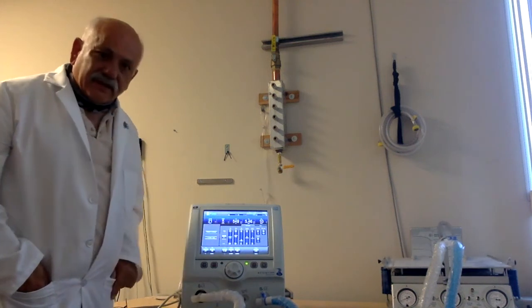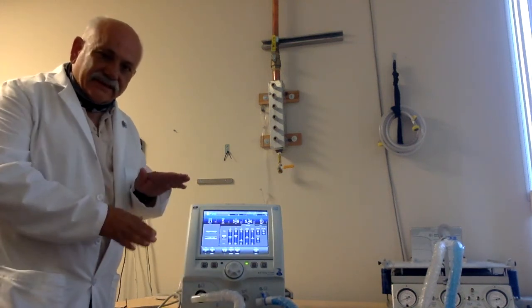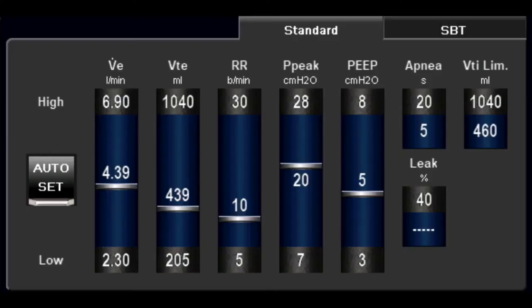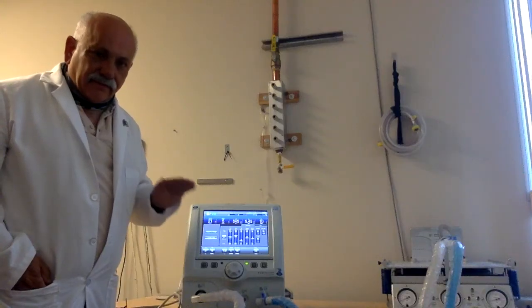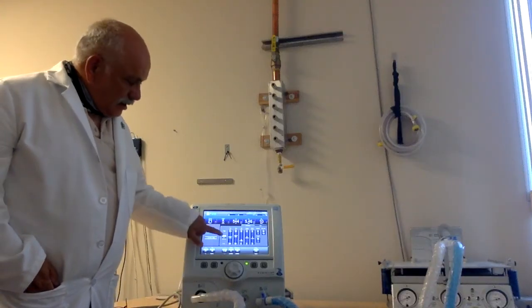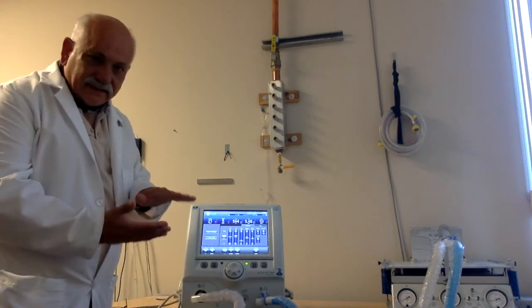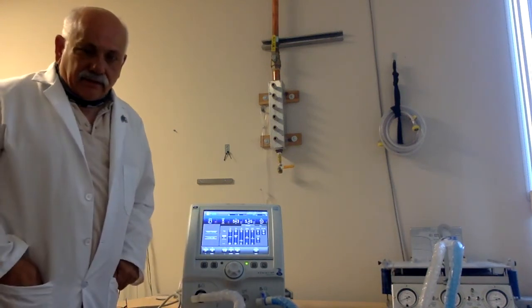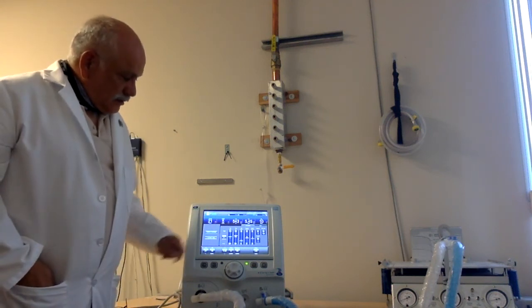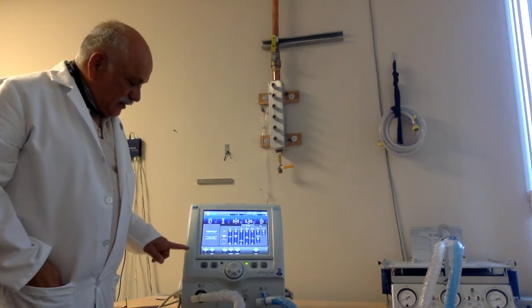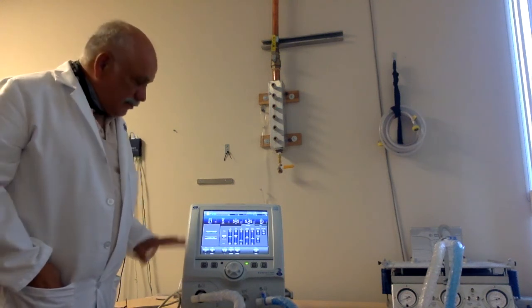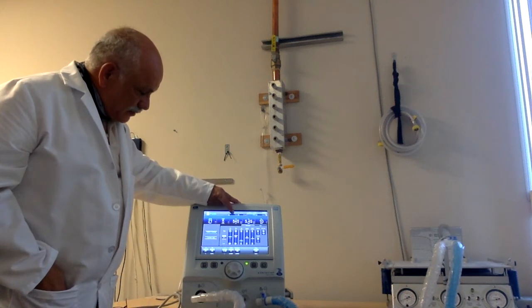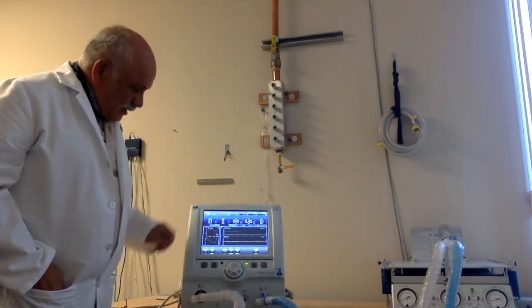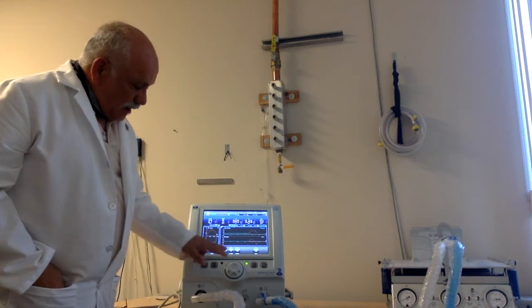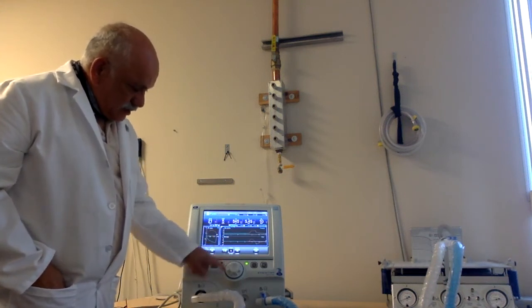If I want to, I can choose an auto set. An auto set will allow me to set parameters below and above the current running variables of the patient, the current breathing parameters, the current breathing of the patient. Auto set automatically sets it, and I can get going to do my other important work. If I did desire, or if I did have a case where the ventilator was alarming, one of the things I love about this ventilator, let's go back to the home page, I'm going to turn off my PEEP. I'm going to go 0 on my PEEP.